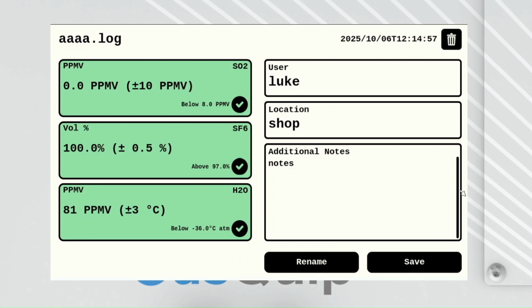On the left-hand side, we have the same layout as before on the home screen. Up here in the top left is the units. We have the module that you're reading, and then the actual reading here, so 0.0 ppmv of SO2 with the accuracy of the sensor, and then the threshold or test limits that we set earlier and whether or not that test limit has passed. For H2O, you can click on the module and it'll toggle the units of the test. So that's helpful if you need to just check how that converts to a different unit.